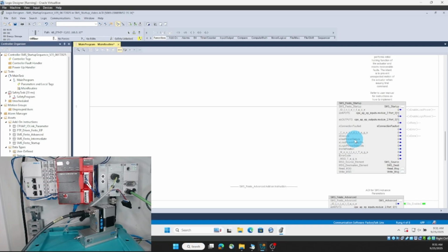manual, it defines that the load power should be turned on after the logic power by 50 milliseconds. So this provides the functionality that if you set this use power relays to 1, that it will drive some relay statuses or relay commands to then turn on external relays. And in the documentation, I explain exactly how to wire this in. But for this example, I'm not going to use a power relay. So I'll leave this as 0, and I will not tie my load and logic power relay statuses to the inputs that confirm that the relay has been closed.